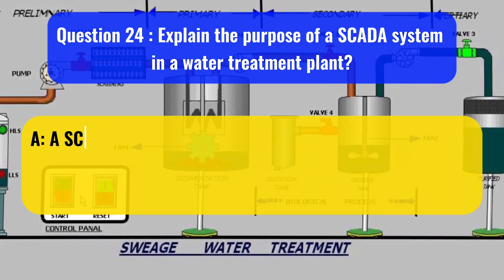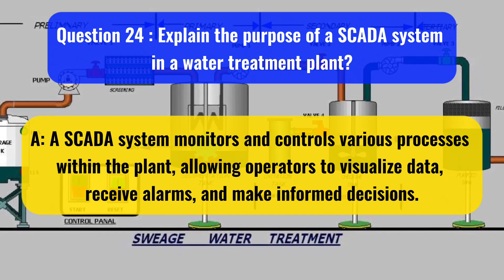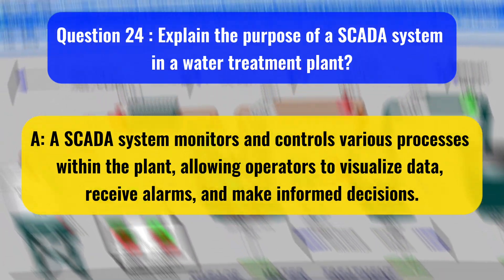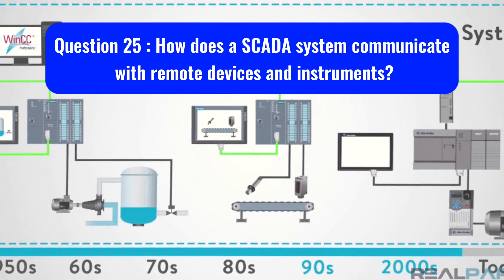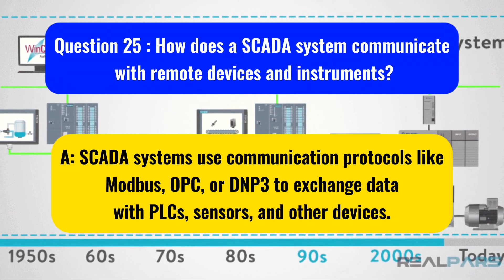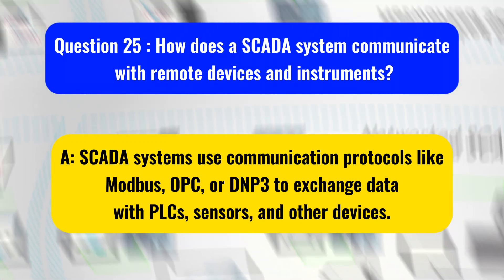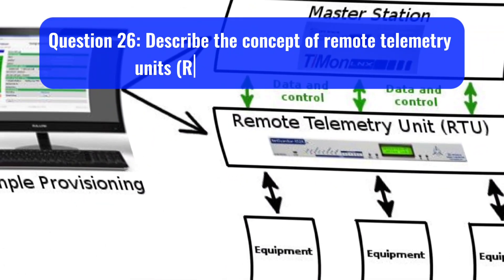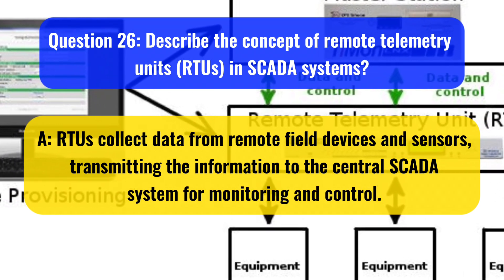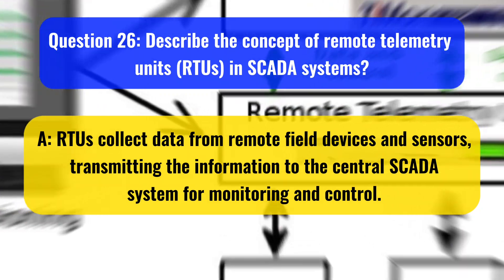Question 24: Explain the purpose of a SCADA system in a water treatment plant. A SCADA system monitors and controls various processes within the plant, allowing operators to visualize data, receive alarms, and make informed decisions. Question 25: How does a SCADA system communicate with remote devices and instruments? SCADA systems use communication protocols like Modbus, OPC, or DNP-3 to exchange data with PLCs, sensors, and other devices. Question 26: Describe the concept of remote telemetry units (RTUs) in SCADA systems. RTUs collect data from remote field devices and sensors, transmitting the information to the central SCADA system for monitoring and control.